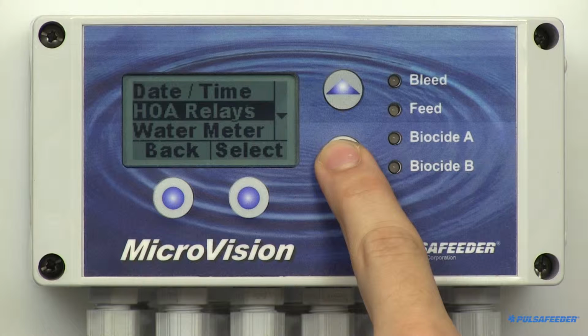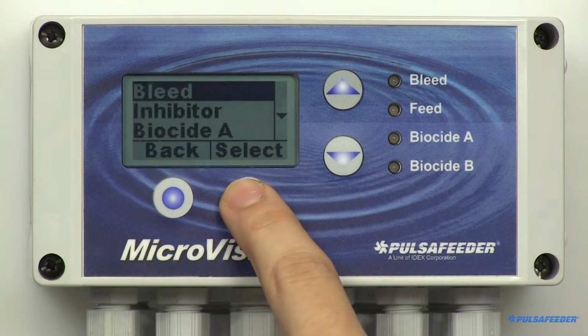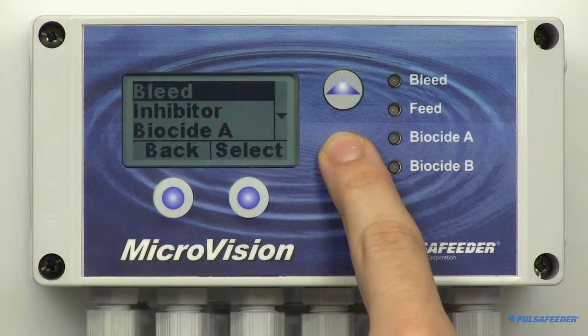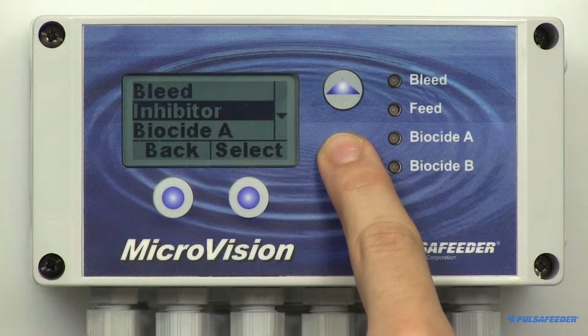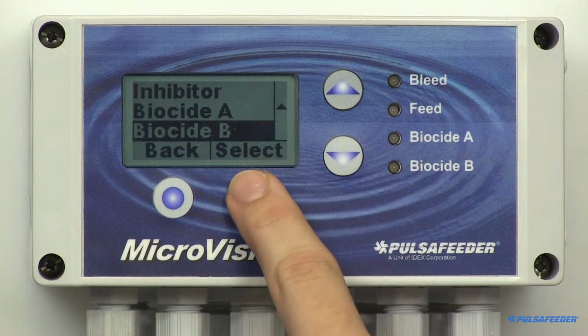The HOA output menu allows one to set the control for the four output relays. This is useful for servicing your pumps or troubleshooting electrical problems. Press Select. Three relays are displayed. To see biocide B, arrow down. Since biocide B is highlighted, let's select that relay.